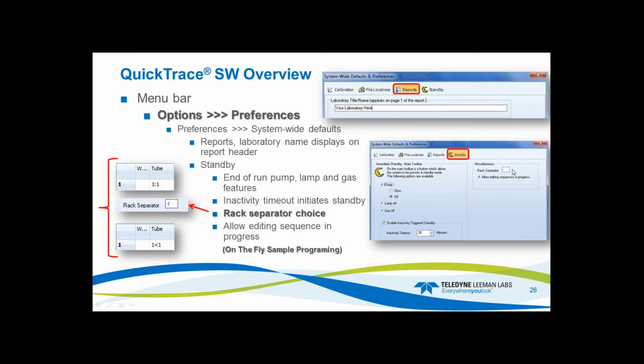And over here, rack locator, or the rack separator. This is for different countries if they want to use different icons to tell you where the racks and tubes are. So typically, here's how it works. The first number is the rack number, from left to right, 1, 2, 3, 4, depending on your autosampler. If you have a smaller autosampler, it'd just be 2. And then the colon is the separator, and then the number behind it is the test tube within that rack. So an example here, I changed it, and it pops up over there.